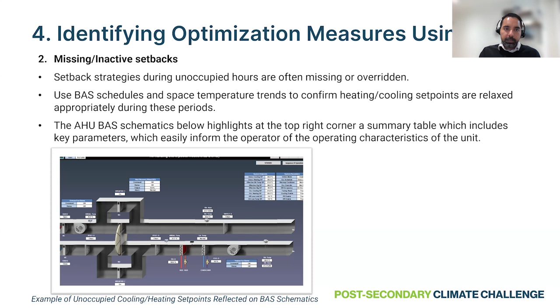Typically, these are reviewed when there's an issue that is reported back to the team, but there's regularly a missed opportunity to look at these on a regular basis to confirm if the measures that apply are implemented or not, or if the system is telling us differently when it's supposed to operate differently. So in this case, these are the missed opportunities that were identified through the BAS graphics review only.